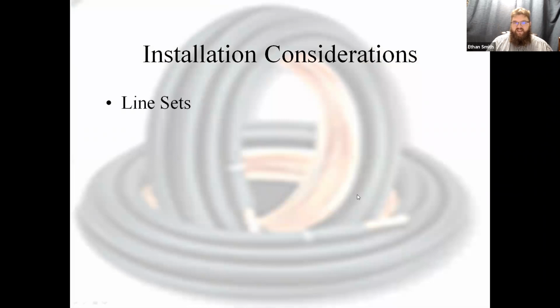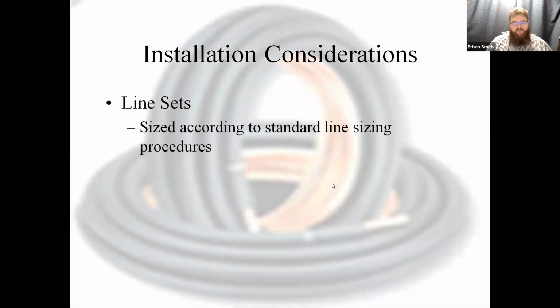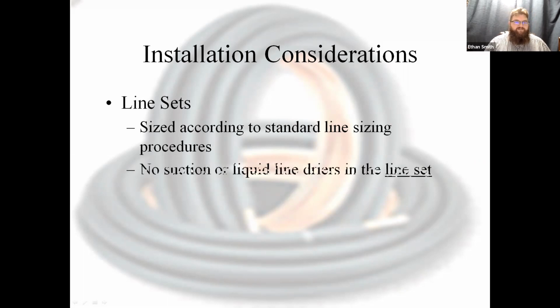Okay, line sets, guys. Size according to standard line set procedures. If you guys ever have any questions about if your line set is adequate or not, please feel free to drop me a line. I regularly size line sets for guys, looking at those long line sets or oversized lines that are existing, seeing if we need to change anything. It's much easier to fix on the front end than it is after you've installed, guys. So reach out if you have any questions about that.